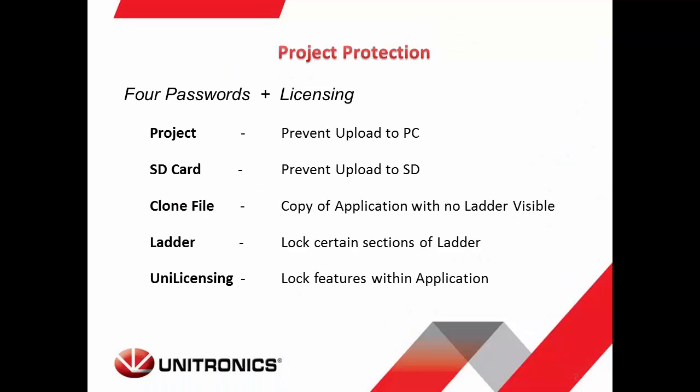There are four passwords that can be set to lock down various aspects of your project. The project password prevents the application from being uploaded from the PLC to a PC. The SD card password prevents your application from being uploaded from the PLC to an SD card.